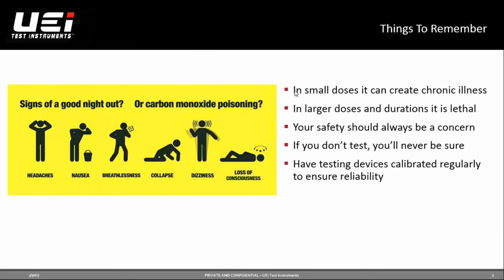Contractors are going into all sorts of places. I've heard horror stories in my travels across the country, you don't know what somebody else has done before you. So if you don't test, you'll never really be sure if there's CO there. And anything testing carbon monoxide should be calibrated regularly, to ensure reliability, because if it's testing a deadly gas, we want to make sure it's spot on where it needs to be.